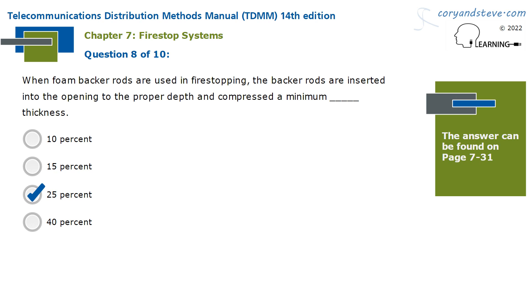When foam backer rods are used in firestopping, the backer rods are inserted into the opening to the proper depth and compressed a minimum of 25% thickness.